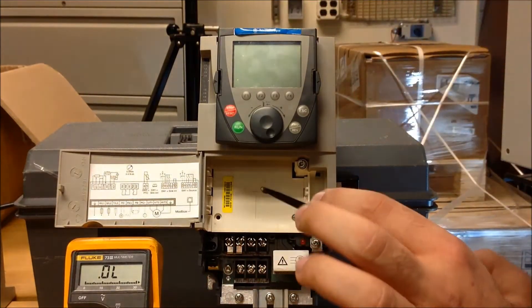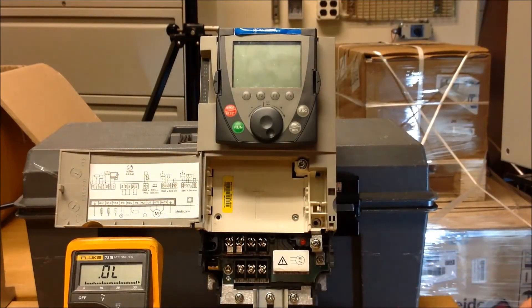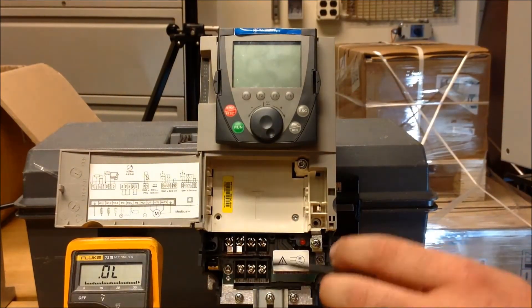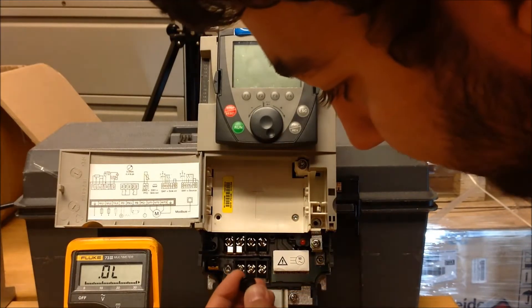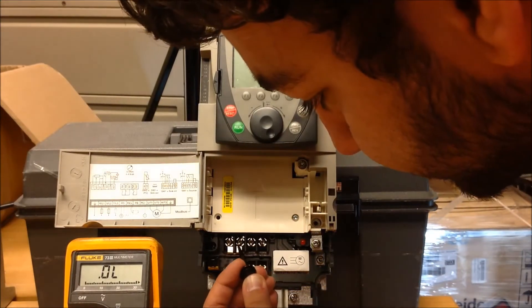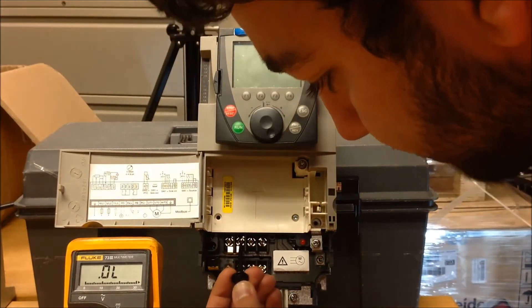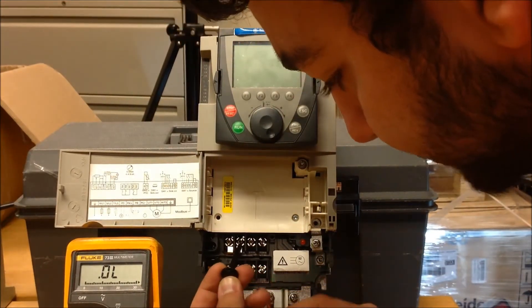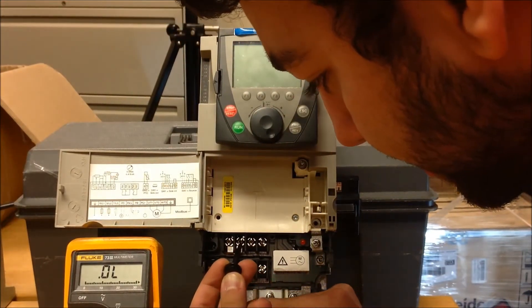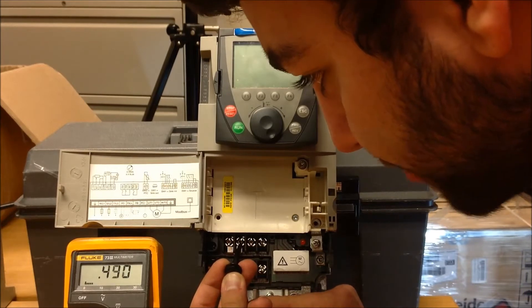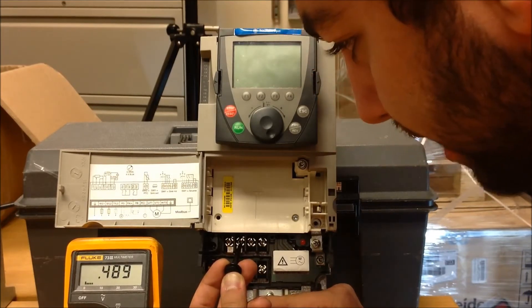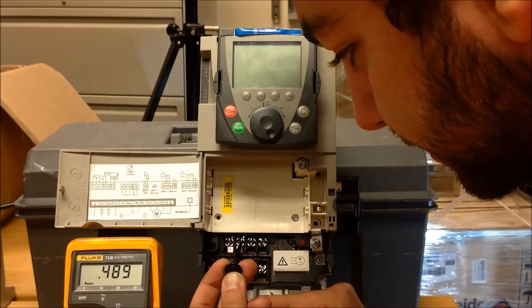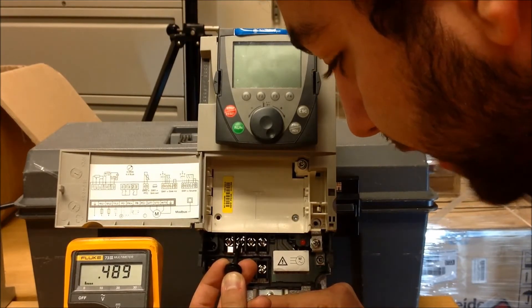Now let's swap your lead so that your negative side of your meter is now going to go to PA plus, instead of the positive side, like last time. And now measure L1, you can see it's about 0.48.